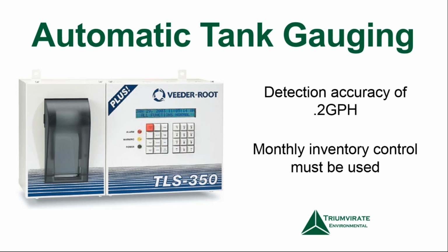The other side to the Veeder-Root is that these also need to be calibrated. So one thing to think about, if you're going to go this route and use an automatic tank gauging system, you need to calibrate them at least annually to make sure that it's reading properly.